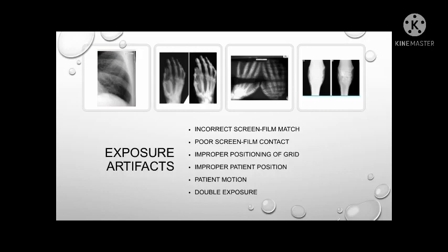Another type of exposure artifact is poor screen film contact. It will appear as smoothness in an area that may obscure some details on the radiograph. It can be checked through a wire mesh test where we expose the wire mesh on top of the cassette. Proper screen film contact produces a high definition image in which all lines of the wire mesh are visible. Without proper contact, the resulting image will show smoothness in certain areas. A warped cassette from heavy objects placed over it will also show smoothness on the affected part.